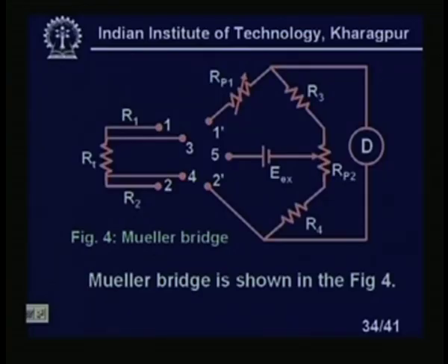You see, this is our Mueller bridge, shown in figure 4. You can see these are our 4 lead wires. And you see that the potentiometers are RP2 and RP1. RP1 is the one we use to balance the bridge, and RP2 is purposefully not used once it is set. It is used to make the resistance of the right-hand side of the bridge.